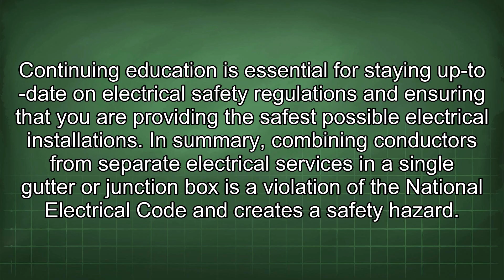In summary, combining conductors from separate electrical services in a single gutter or junction box is a violation of the National Electrical Code and creates a safety hazard. Different service voltages can cause short circuits or fires. Troubleshooting becomes difficult when services are combined.